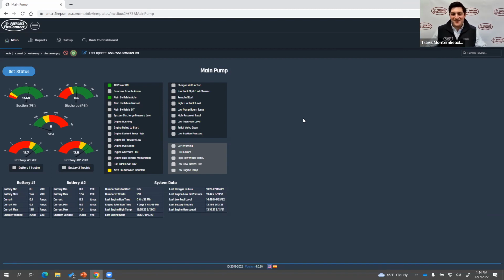Code is being updated though. NFPA 25 says right now that somebody has to address an issue within 5 minutes, which means that somebody needs to be there on site. Next year, that's changing to 4 hours, which means that somebody doesn't necessarily need to be there right away, but they need to be able to get there. So things like remote monitoring open up that potential, but it still doesn't replace the ears, the nose, and the eyes test. So adding a camera, we see as the next logical step.